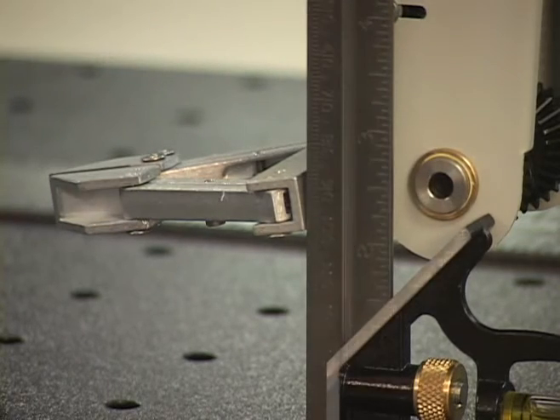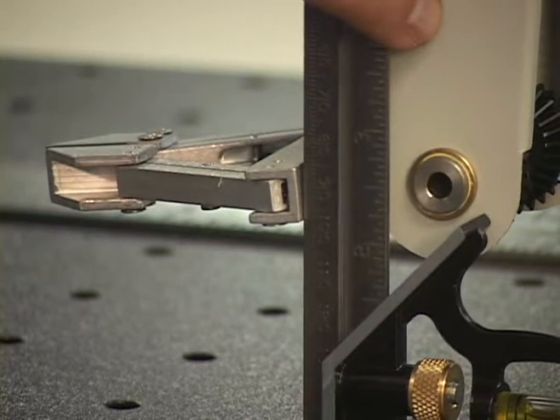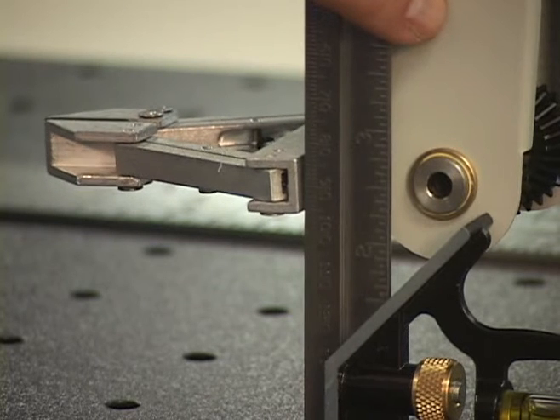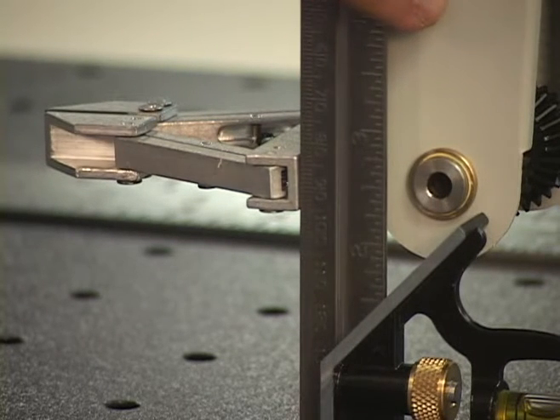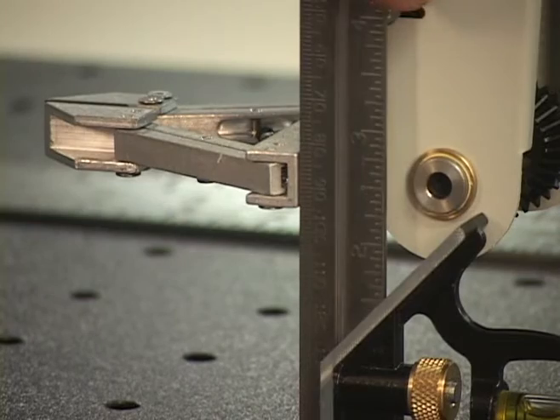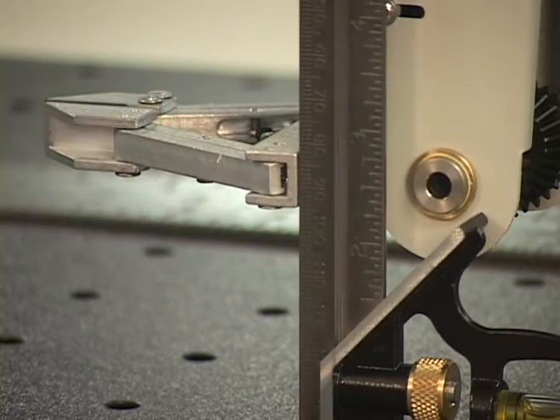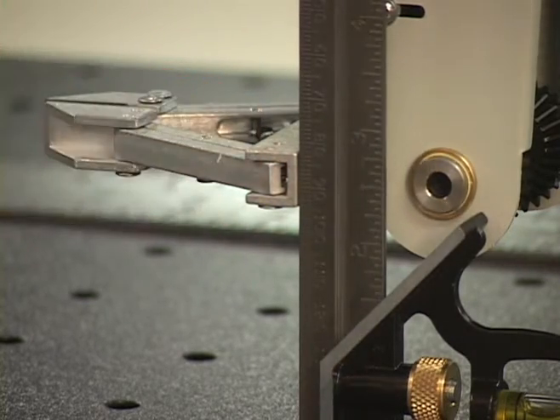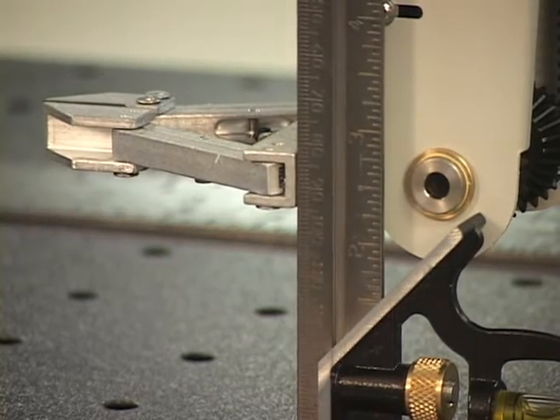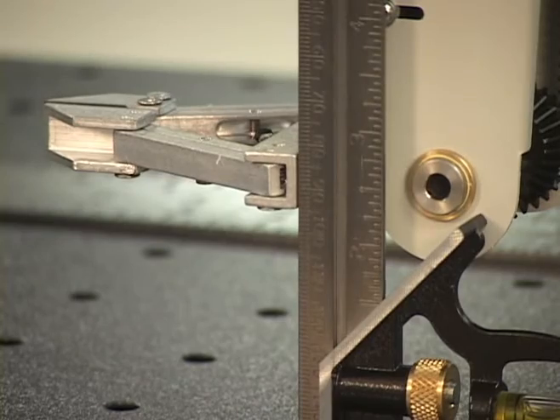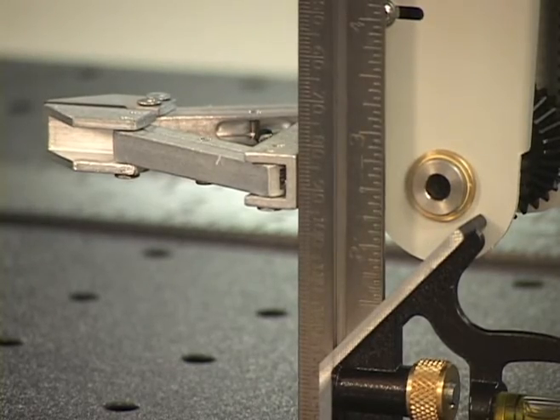Calibrate the wrist pitch articulation so that the gripper is perpendicular with the work surface. Position the edge of the blade of the combination square against the side of the gripper. Move the pitch articulation until there is no clearance between the edge of the blade and the gripper. Note: if the pitch articulation is moved, you will have to perform this step again. The opening of the gripper does not require calibration.